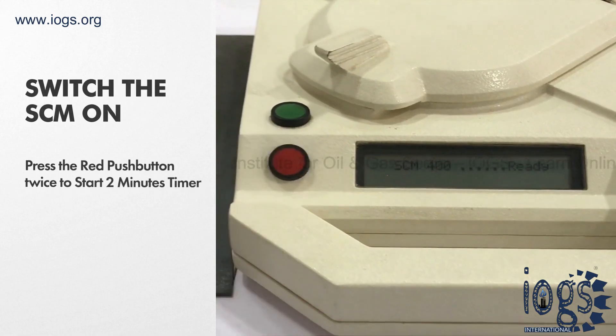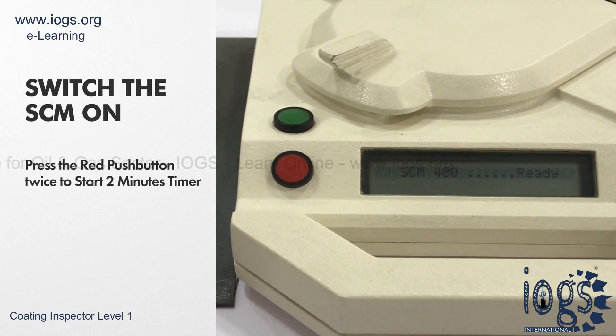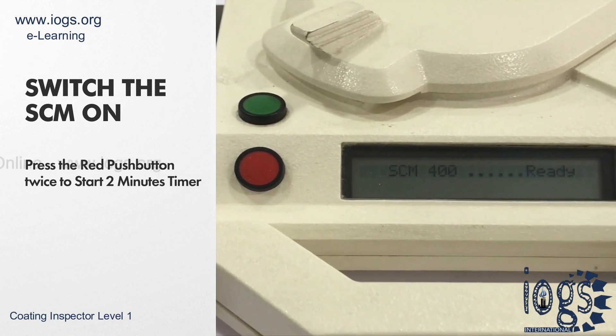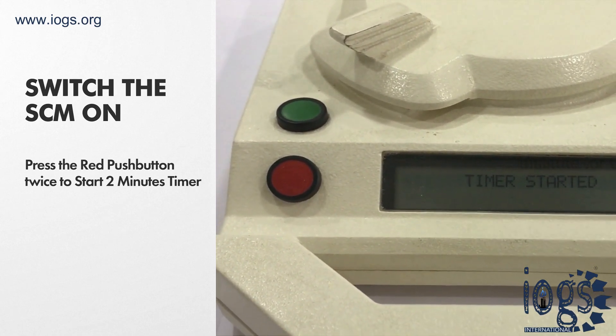To start the timer, switch the SCM on by pressing the red push button once. Upon switching on the SCM, the screen will display 'SCM ready,' indicating that the device is ready for use.